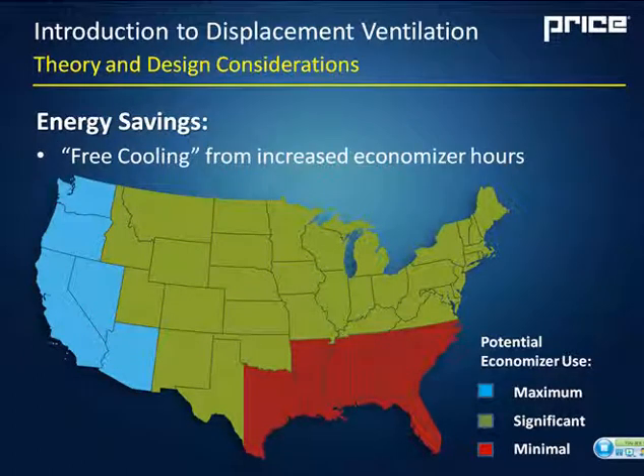Now, I mentioned energy savings and the popularity of displacement ventilation on the West Coast, and that's mainly due to free cooling. Free cooling is just a term that means basically you're able to pull in outdoor air and use it to cool your building. Whereas with a mixed system where you're using 55-degree air, there's really a limited amount of time of the year that you could be pulling in air where it's 55 degrees. With a displacement system, if you're looking at places like California, Washington, and Oregon, they have a significant portion of the year where they're able to run the economizer, just pulling in outdoor air and not using any mechanical cooling. So the reduction in energy usage is significant for those areas.